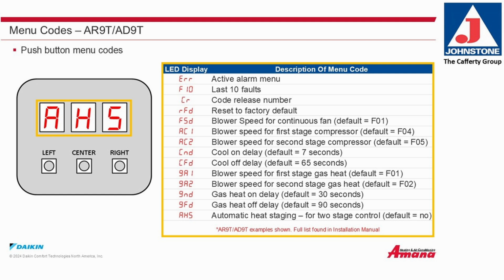GA1, blower speed for the first stage of gas heat, default F01. GA2, blower speed for second stage gas heat, default F02. GND, gas heat on delay, default 30 seconds. GFD, gas heat off delay, default 90 seconds. AHS, automatic heat staging for two-stage heat control, default no. The examples shown are for the AR9T, AD9T. Full list is found in the installation manual.